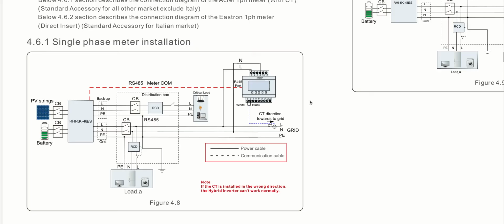get a 3-phase kilowatt hour meter and plug it into the single phase Solis. Now the thing about this Solis inverter, they're not very good with the instructions, especially these ones, because they don't tell you that in backup mode, if the grid goes down, see how they've drawn the backup circuit separate from the grid circuits? They're all going back to the same switchboard. Well, you're not going to put in a switchboard and rerun final sub-circuits to it. So the big problem here is if you've got a multiple earth neutral in the main switchboard, and this one decides to make a multiple earth neutral, which it does if the grid goes down and it goes into backup mode, it'll join the neutral to earth here in the inverter. So now you've got a parallel earth and neutral path.